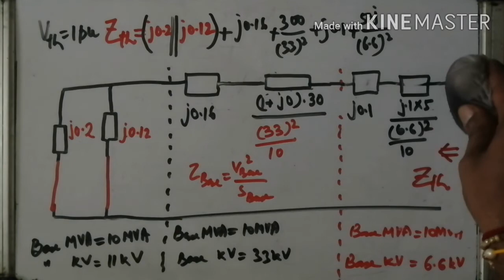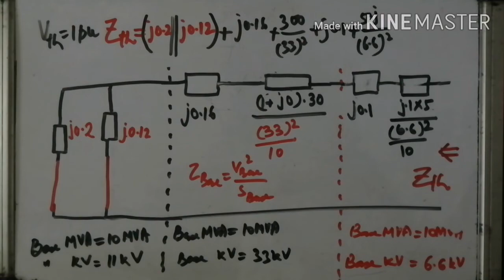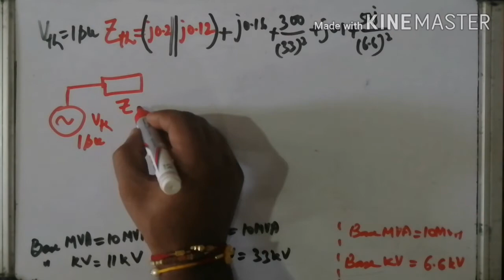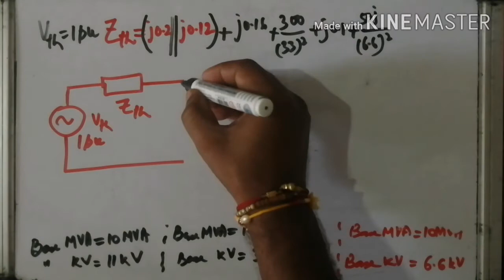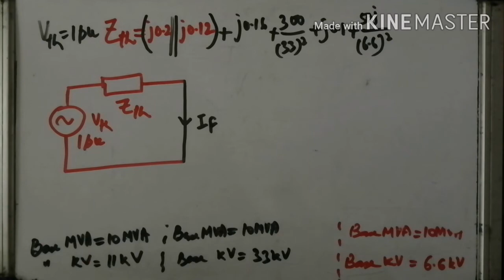Now I am going to draw the Thevenin equivalent circuit. The Thevenin equivalent circuit contains a source having the value of 1 pu, it's your VTH. Then an impedance, that is ZTH, and then the point where the fault current will flow. IF is the fault current, and the value of IF is given by the formula V divided by Z, right? Once you calculate the value of ZTH over here, then we can calculate the value of the fault current.